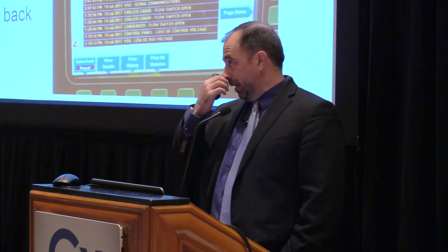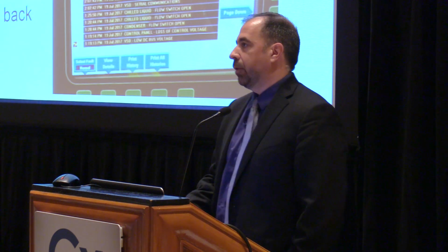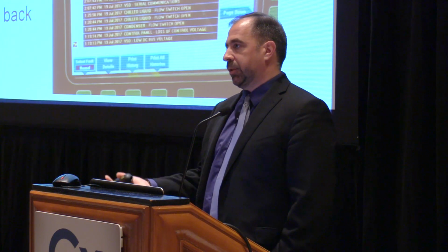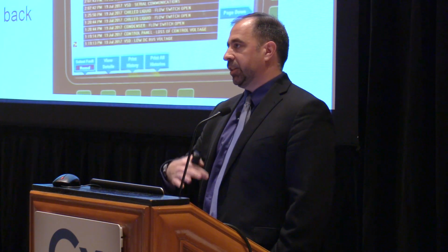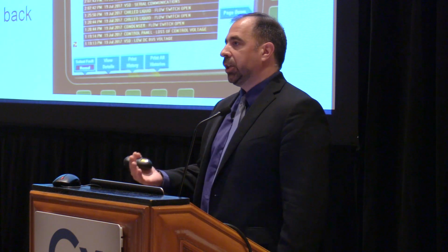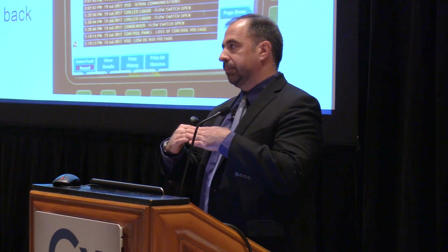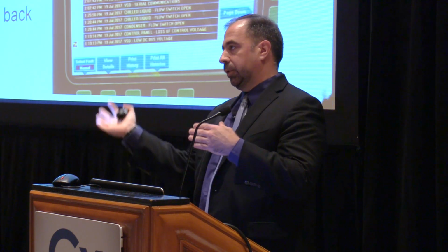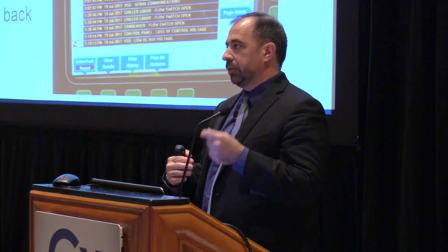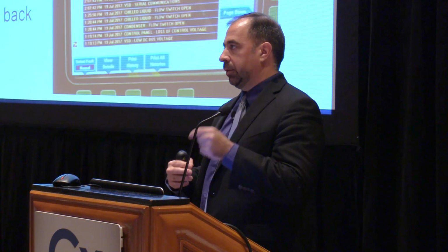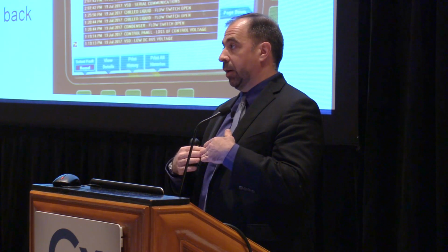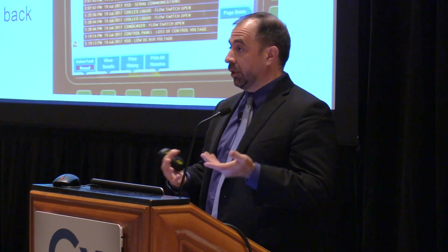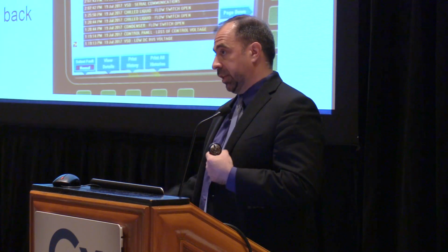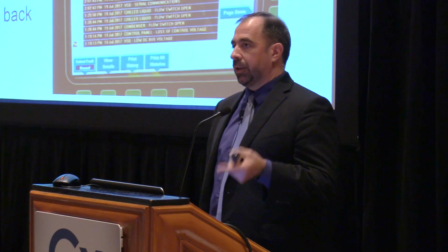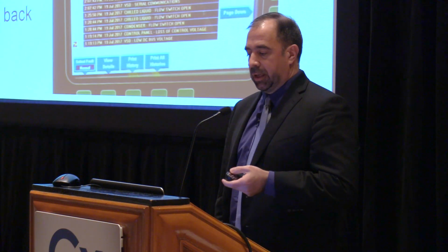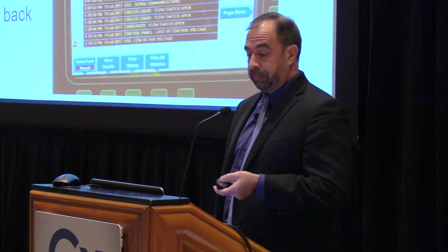The comment was about open transition transfer switches versus closed transition transfer switches. I didn't get into that level of detail, but closed transition basically connects the two sources before it switches, so theoretically there's either a much smaller or no interruption of power. But that's more expensive too, and there are other issues that can come along with that. So that's an important conversation to have, making sure the owner knows what they're getting and why.